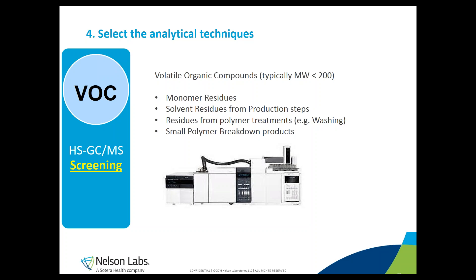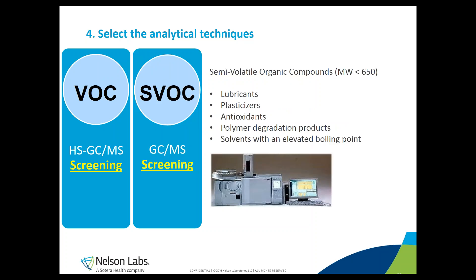To capture very small, generally volatile compounds, it is advised to use headspace gas chromatography coupled to mass spectrometry. Typical small compounds include monomer residues, solvent residues from production steps, residues from polymer treatment, and small polymer breakdown products. Mid-sized, less volatile compounds — called semi-volatile organic compounds — are analyzed by gas chromatography methods. Typical compounds here include lubricants, plasticizers, antioxidants, polymer degradation products, and solvents with an elevated boiling point.